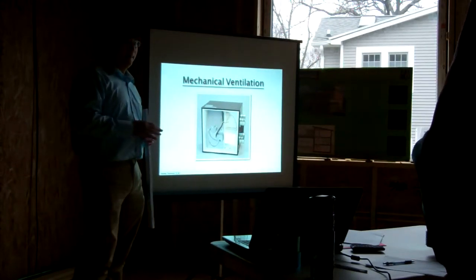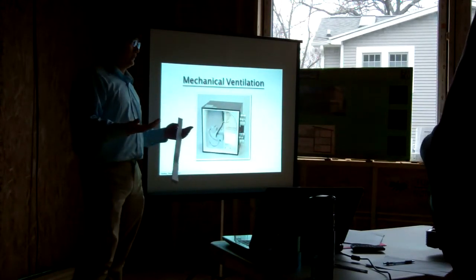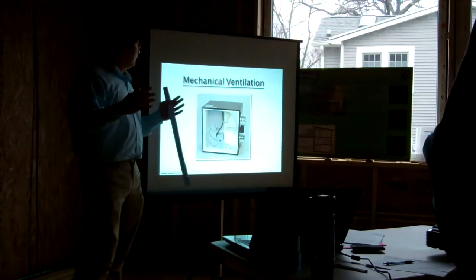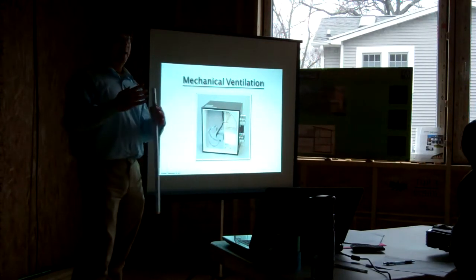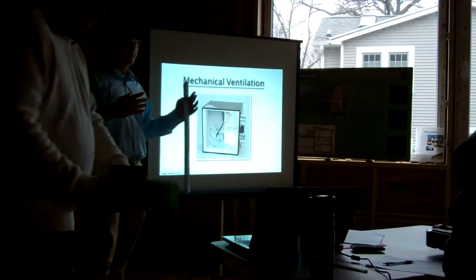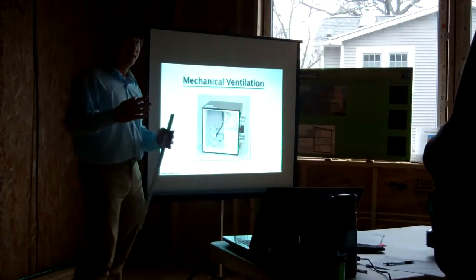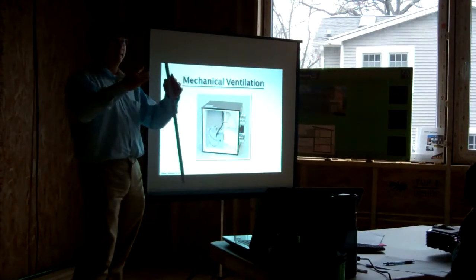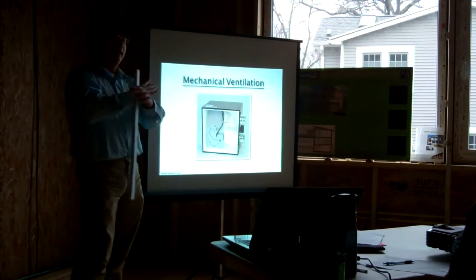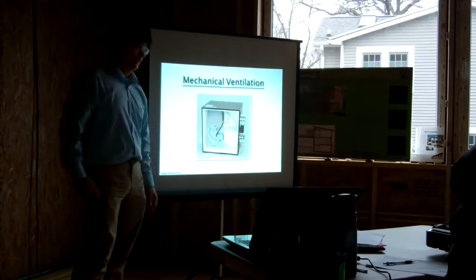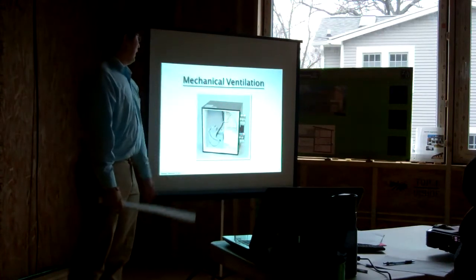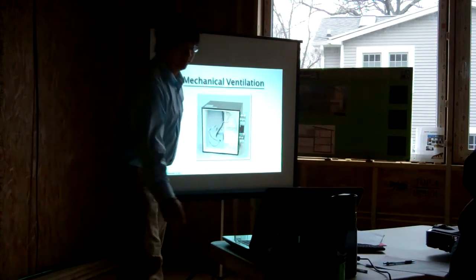Why is it called an energy recovery ventilator? It's because as the stale air goes out, if you don't recover some of that heat, you have to reheat the fresh air coming in. So what it does is transfer that heat as the two streams of air intersect, and the recovery rate is up to 95%. So this is very efficient.